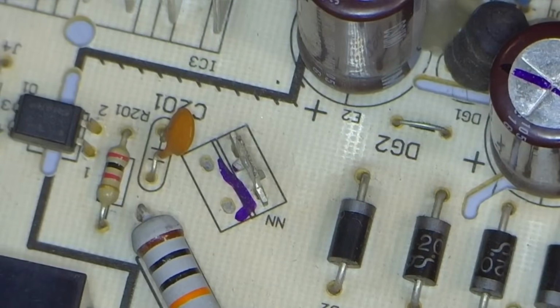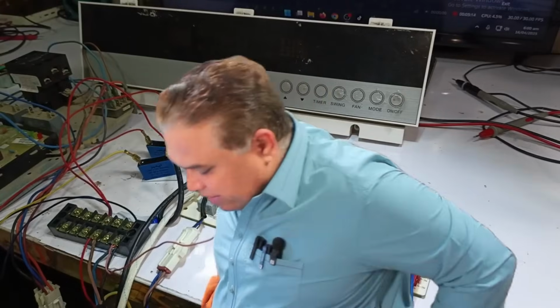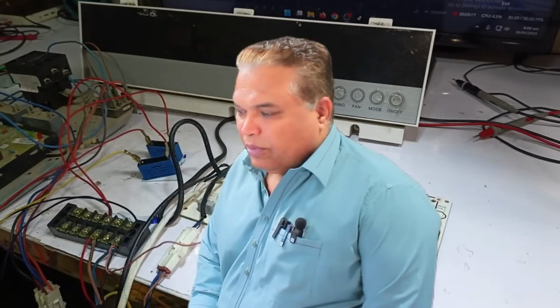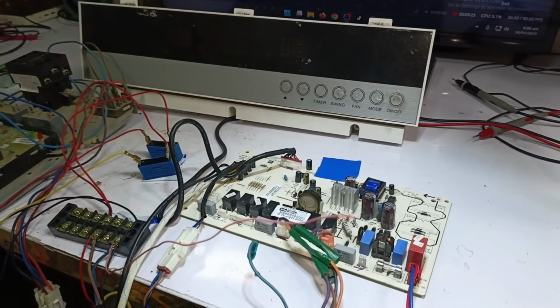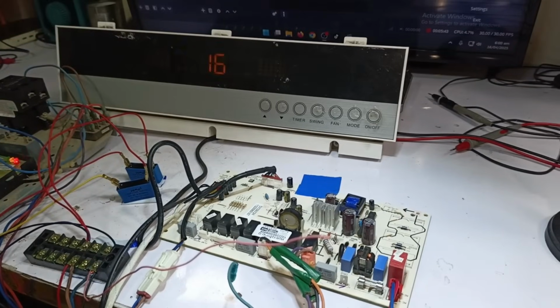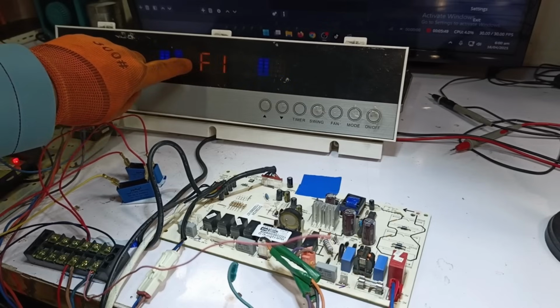You need to observe this test carefully because it will give us a lot of clarity on what we need to do next. If the relay is confirmed to be fine, then we need to find out what other fault could be present at this point. Now, what we have done is connected the wire, but the power supply has not yet been turned on. You must carefully observe the screen now. I turned on the system, and it showed 16 degrees, but immediately after that, the F1 error started appearing.